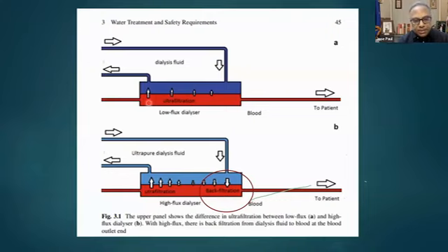The pressure difference between the two compartments is maximal at the start of the blood compartment, and as water moves across into the dialysate compartment, the pressure in the blood compartment decreases, and there is a gradual loss of the transmembrane pressure. However, this transmembrane pressure is generally maintained in a patient undergoing low flux hemodialysis. So back filtration generally doesn't happen to a great degree in low flux hemodialysis.